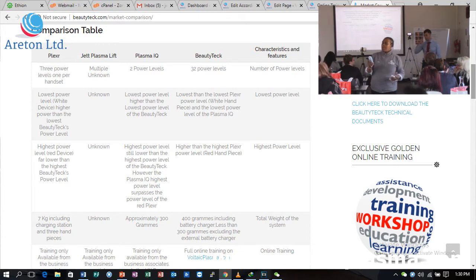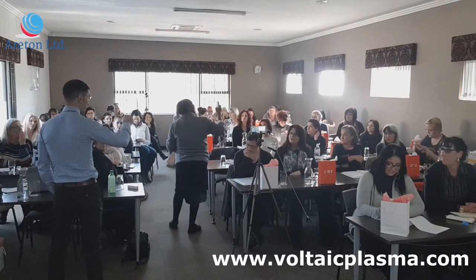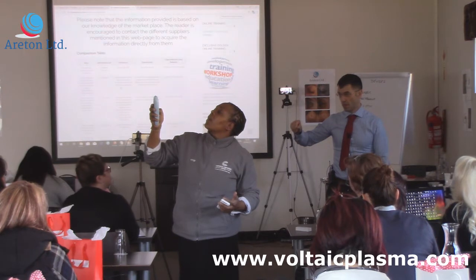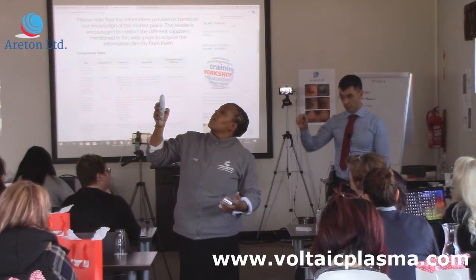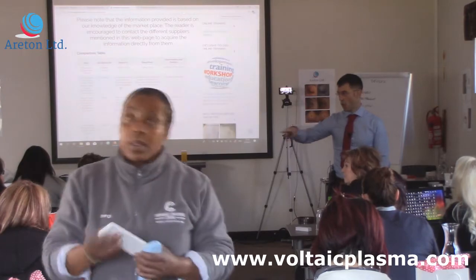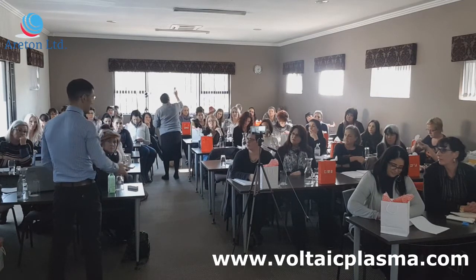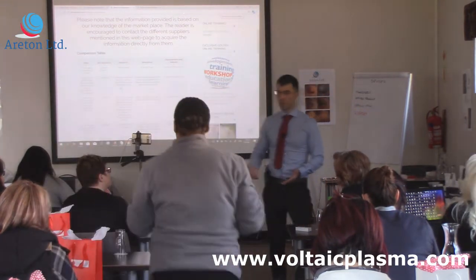So yes, the piece of meat is very, very important, because even the Plexr guys have done it for several years on the piece of meat. This is where the surgeons have actually practiced on their electrocautery devices. So the piece of meat, chicken skin or anything, don't take as a gimmicky thing. It's been used for several years, also by surgeons. When surgeons practice on electrocautery, instead of practicing on people, they practice on meat. They take a steak and they start burning the steak or cutting the steak using the electrocautery device. So it's a very, very important exercise.